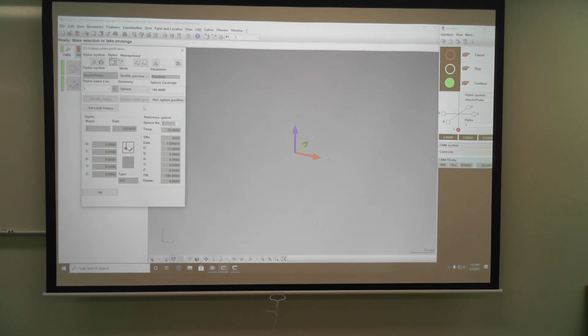So this is something that I pretty much make this mistake every single time I go to calibrate a stylus. I'm under the impression that because I haven't moved that calibration sphere, the software must know where that is. But every time you turn the computer off and turn it back on again, it forgets where that calibration is. And I've tried putting that on our image, it doesn't work. So every time before you do a calibration in each session, you have to tell it where that calibration sphere is one time. If we left the computer and the machines on all the time, we'd never have to retell it where this is with the master probe. But we do here, because we turn them on every time.